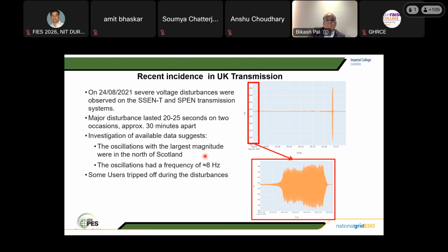Recently in the UK, there were 2 oscillations within half an hour, each lasting about 30 seconds, at 8 Hz. Now, if you look at this oscillation, the oscillations are in the kilovolts of the RMS value. So it's a 400 kV circuit, right? It's going up to 430 and down to 360. This is not involving any mechanical rotor, okay? It's very strange. And that is expanded. So what is the source of this oscillation? That is essentially coming from the converter control.